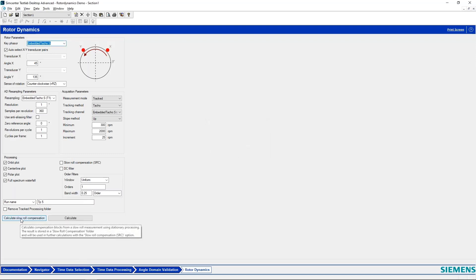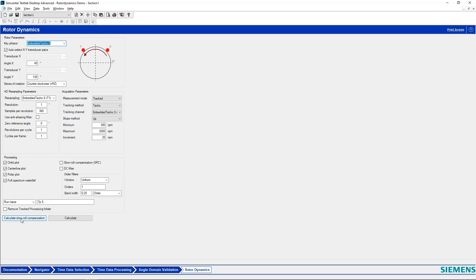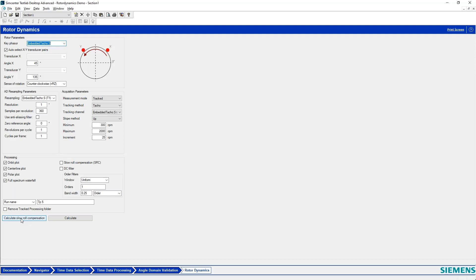Note that I can also do a slow roll compensation. This slow roll compensation, essentially what it does is, all equipment that we'll be measuring has imperfections or glitches on it. It might not be perfectly circular, there might be some scratches on it and so on, and these will show up in our vibration measurements as noise essentially. So with the slow roll compensation, you would record some data at a low rotational speed where there aren't really any dynamic forces at play, so there's no shaft vibration. All of the displacement that we're reading is essentially due to the glitches in the shaft, and then we subtract that from our dynamic measurement data.